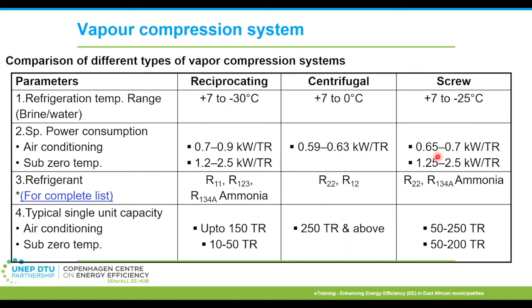The key takeaway from this table is to see what capacities are available for what type of compressor systems are in place. This is not limited - there's a lot more information you can look through later. For example, the specific power consumption these days can be as low as 0.47 kilowatt per TR. There are other systems too, but these are the most common ones you'll come across.